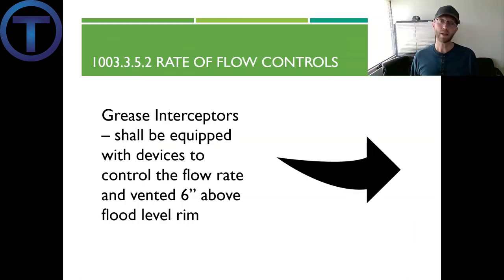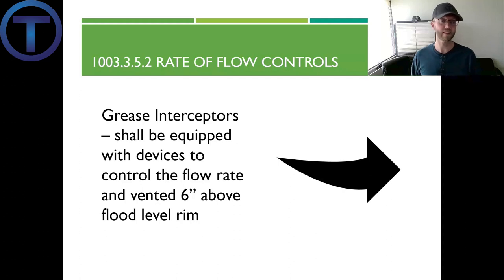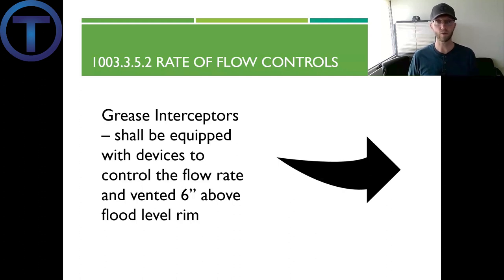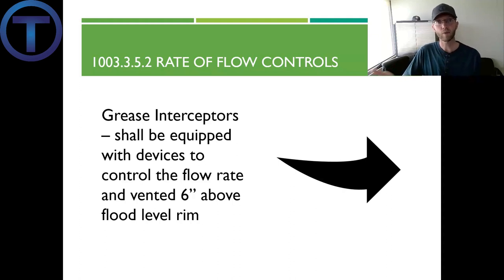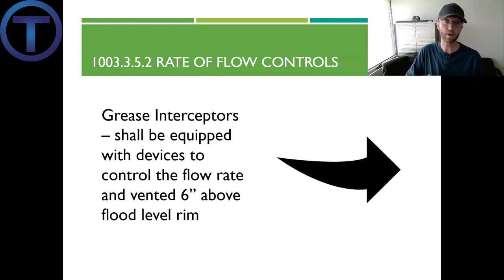Section 1003.3.5.2 talks about rate of flow controls, stating that grease interceptors shall be equipped with devices to control the flow rate, and they have to have a vent that goes at least six inches above the flood level rim. This way, as we're processing all that grease, we can control how much is being processed at a time by slowing the flow.